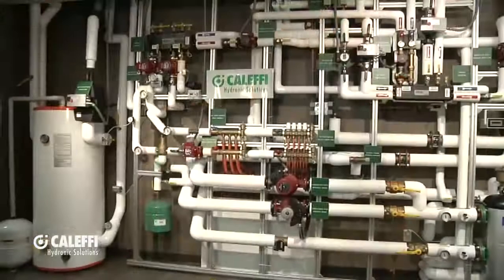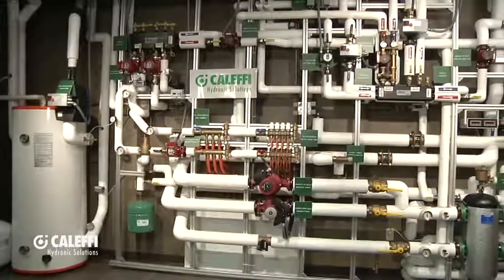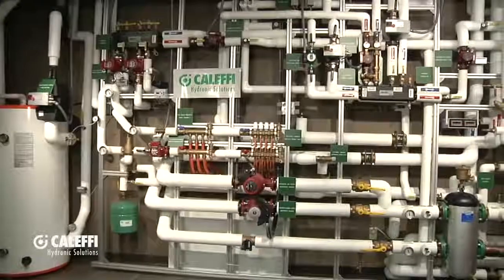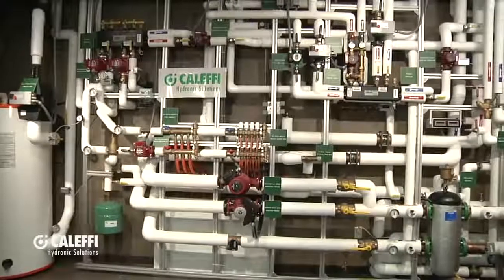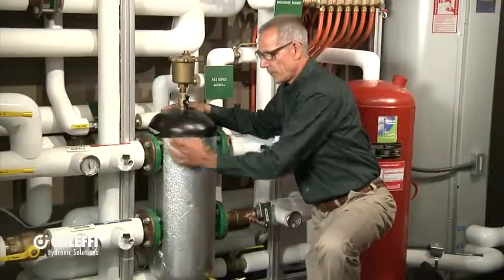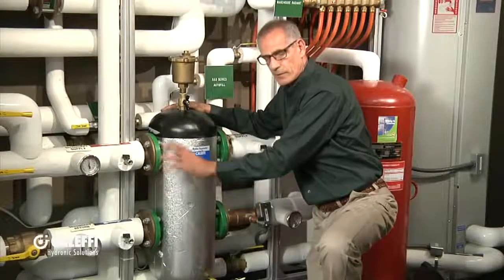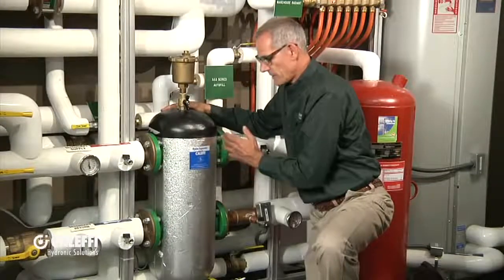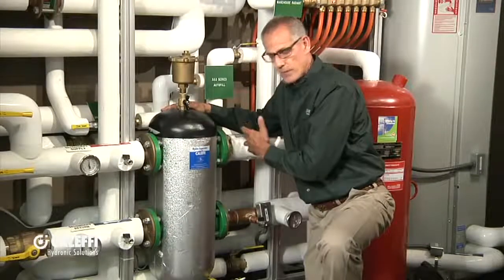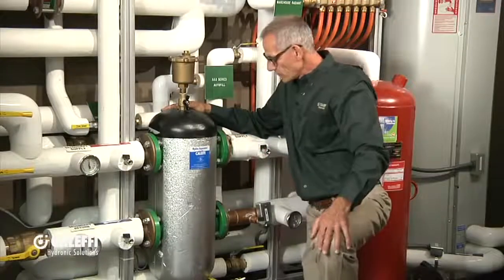So 4 boilers, 4 different pumps over there, and they can flow through here without conflicting with one another on the boiler side. Over here on the distribution side, we've got a whole series of pumps on this wall - air handlers, radiant zones, panel radiators. Regardless of how many pumps kick on and off, it's not going to induce any flow into our boiler side circuit. That's what one looks like installed.